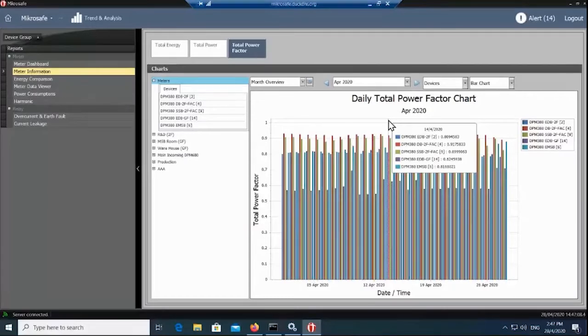And for those where the power factor is rather low, maybe you need to do something. I saw here there's a 0.6 something, right? Yeah, number 14, the 0.6, I think it's rather low. So from here you can do something before anything happens.